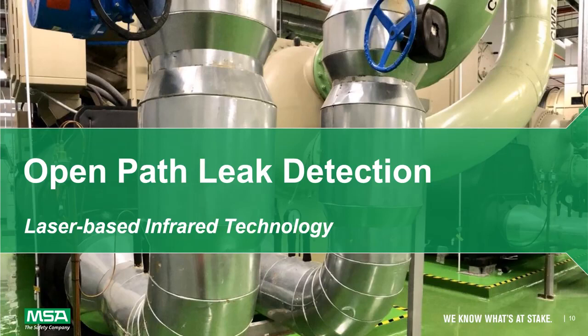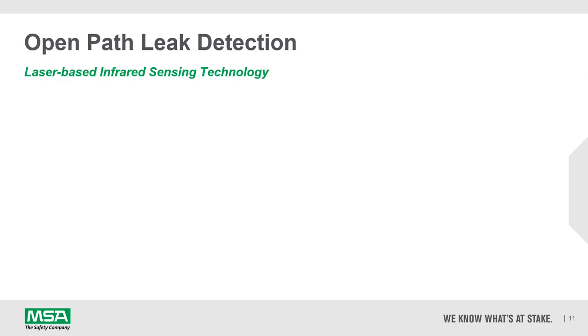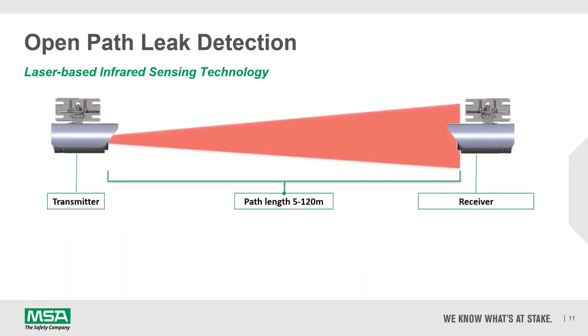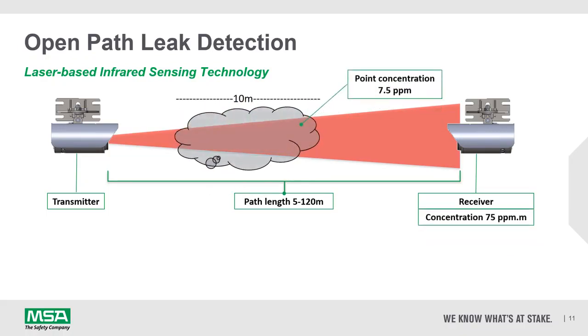Now let's look at open path ammonia leak detection using laser-based infrared technology. Open path ammonia leak detectors using laser-based infrared sensing technology consist of a transmitter sending infrared light to a receiver, and for ammonia this can be done over path lengths of 5 to 120 meters. In terms of gas concentration, if you picture we had a gas cloud of ammonia 10 meters in width whose concentration was 7.5 ppm, then the output on an open path device would be 75 ppm meters.